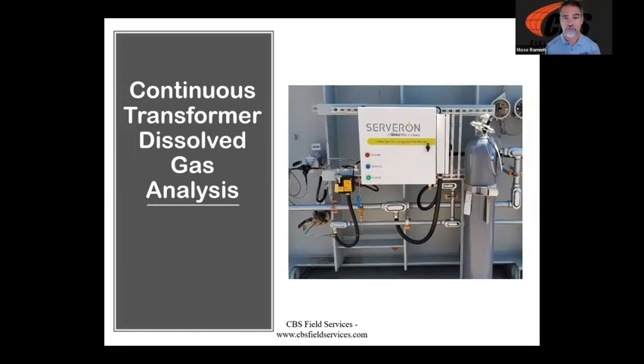So there are devices out there, once again, from several manufacturers. This is just one that I happen to have a picture of, that are going to continuously monitor the oil. So basically it's sampling that oil all the time, running it through an analyzer, and then once again will alarm us. This is typically done for things like hydrogen, acetylene, some of your dissolved gases. And from that standpoint, it basically gives you the health continuously on our critical transformers.